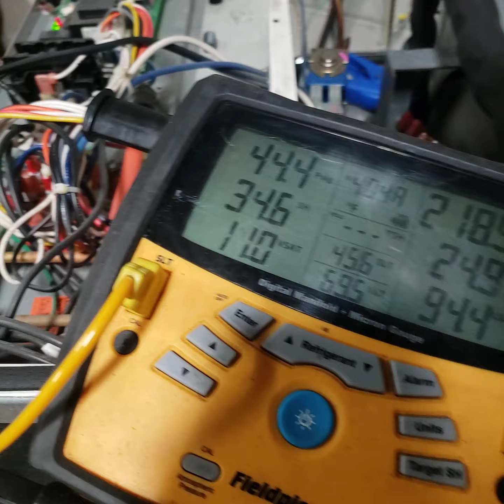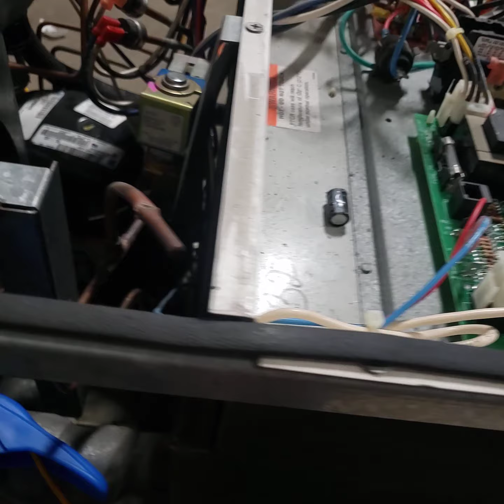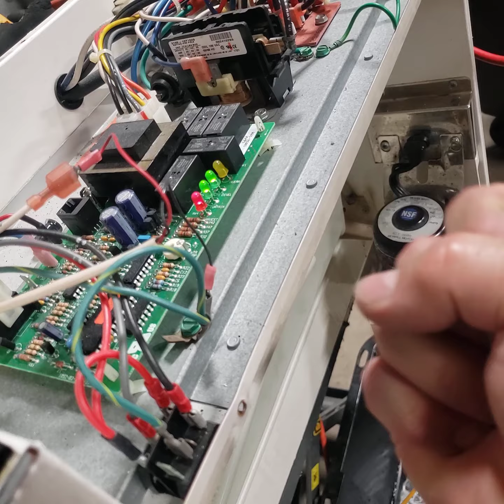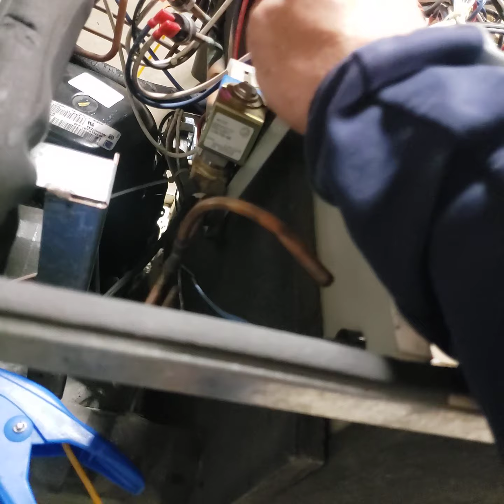So now we start building ice, because look, it's 11 degrees inside the evaporator, right? And one thing that came to my mind, I like to help you guys in case you need to diagnose if the hot gas bypass solenoid valve is broken. When the harvest comes, when the water probe thickness senses enough ice thickness, it will send a signal to the control board. Control board will energize immediately this guy.